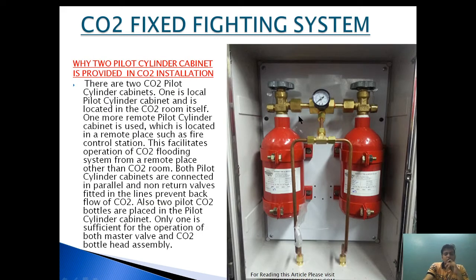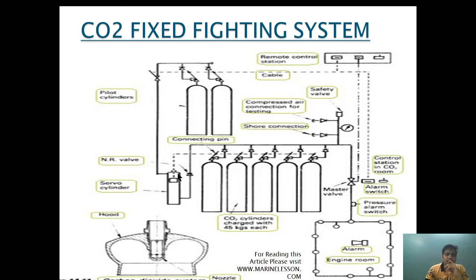When the servo cylinder is activated, it punctures the CO2 bottles in bulk via the connecting pin. The bulk CO2 is released and passes through the master section valve and is injected into the affected area for quick fire extinguishment. Two pilot cylinder bottles are provided as a type of redundancy — if there is any leakage in one pilot bottle, the other can perform the action. Each individual pilot cylinder has the capability to actuate the servo cylinder.